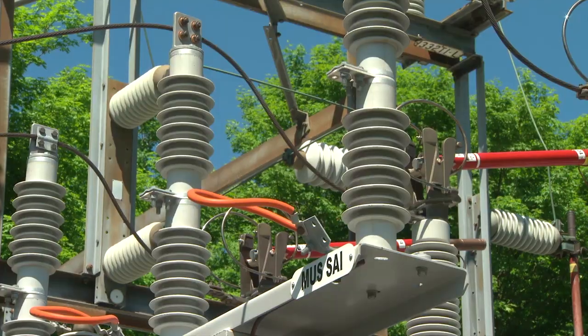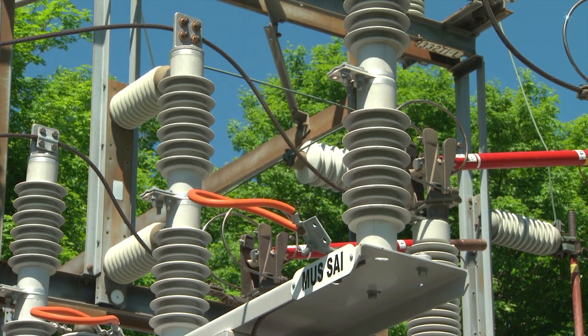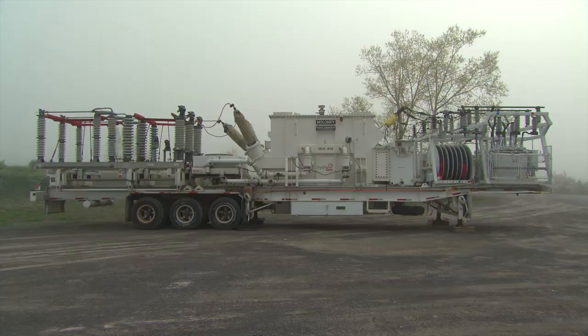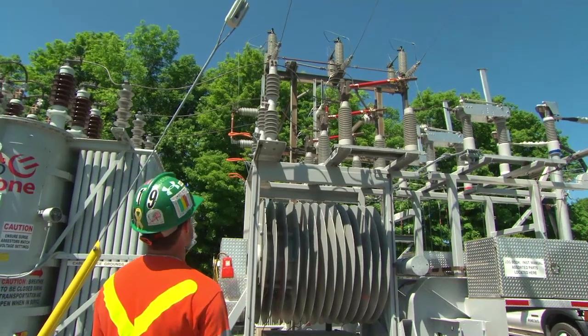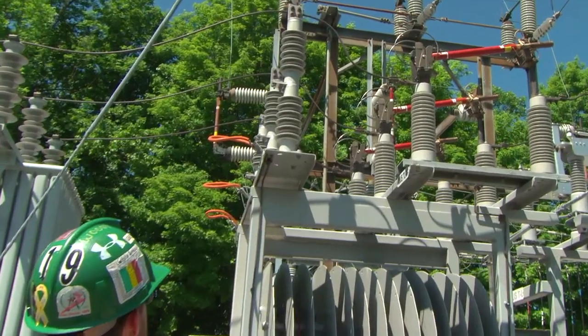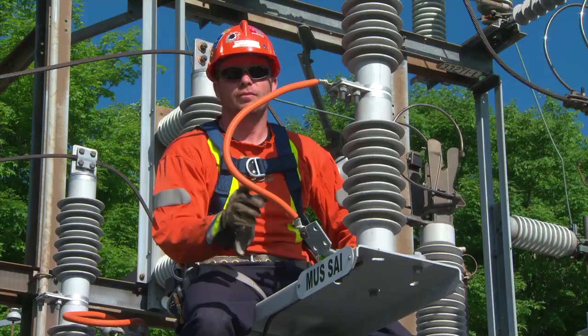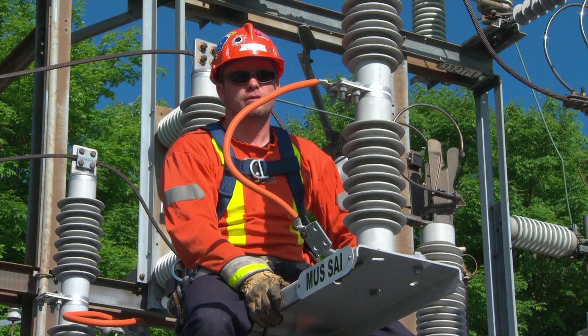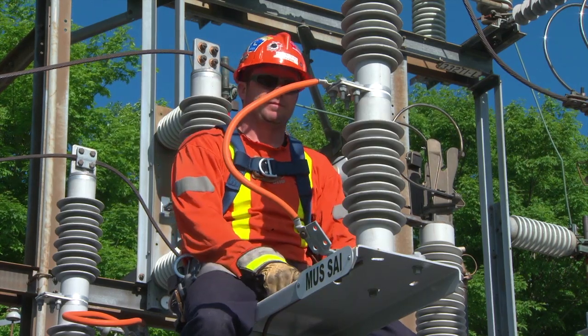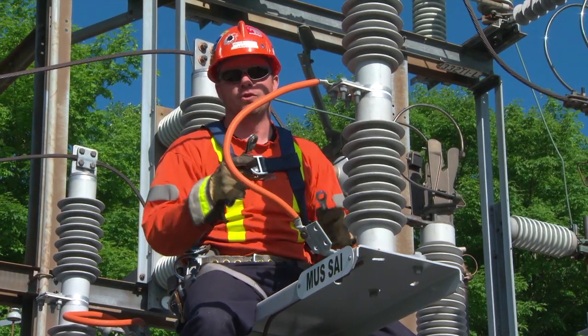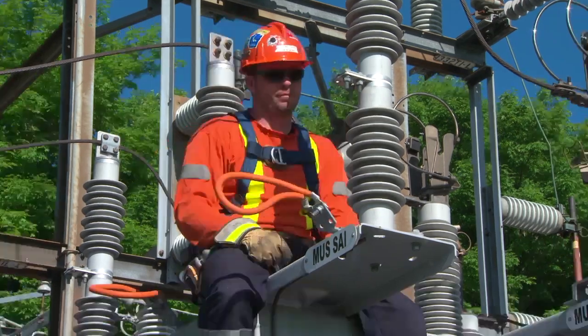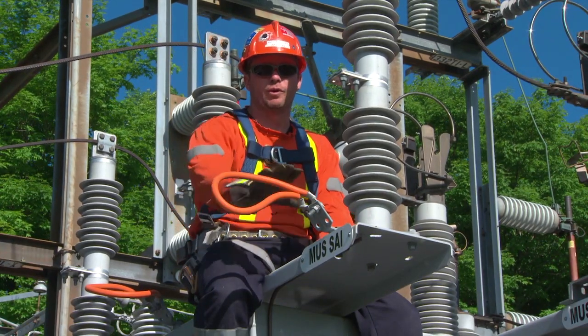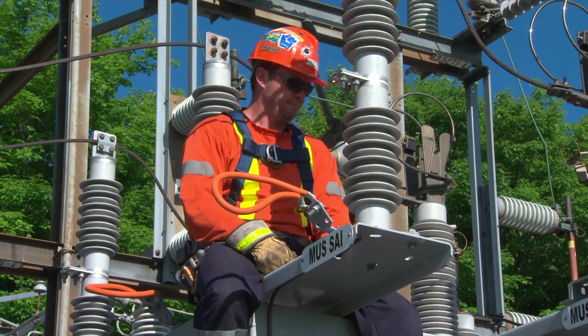Surge arresters protect the transformer from any damage due to lightning strikes or overvoltage. There are 2 sets of surge arresters on every mobile. One set for the primary side and one set for the secondary side. Some surge arresters have multiple voltage level options and will need to be set to the same voltage level as the MUS transformer. This is done by connecting or disconnecting a shorting jumper.